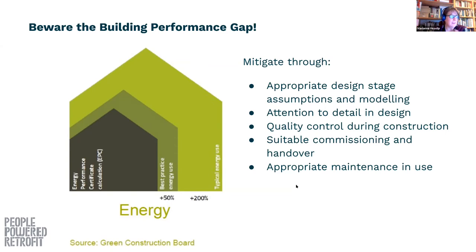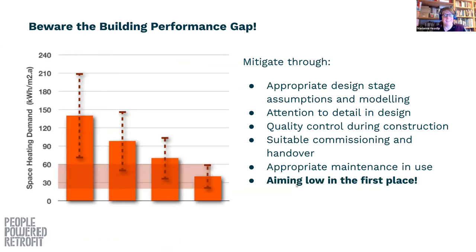If you've got a combi boiler you might want to go and check what your flow temperature is set to tonight. Maintaining things while they're in use matters too — a wall with a leaking gutter means all the stonework or brickwork gets wet and will have a worse U-value than a dry wall. One of the things that can really help is by aiming low in the first place: if you've reduced your overall heating demand significantly, then being 10 or 20 percent off on a very small number is much less of a worry than 10 or 20 percent on a much bigger number.